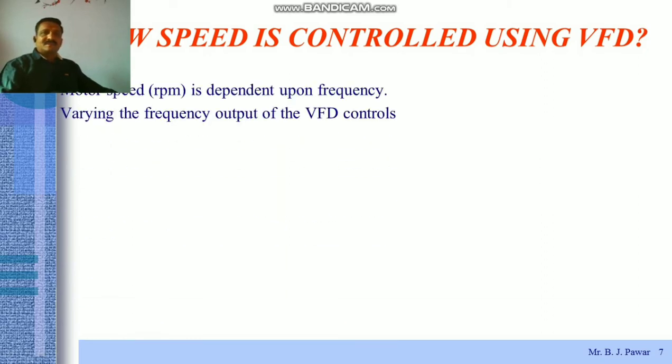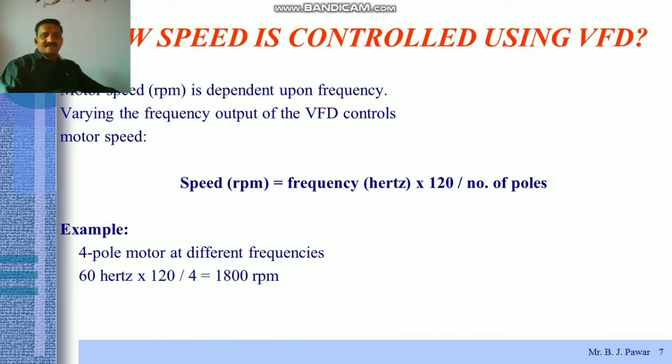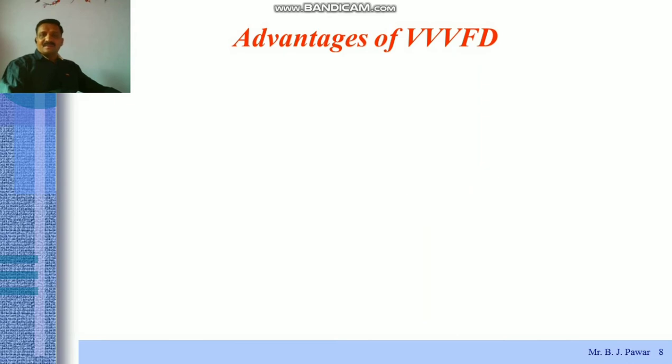So how the speed gets controlled using this VFD? Here few points are highlighted. Motor speed, that is RPM, is dependent upon the frequency of that AC supply. By varying the frequency output of that VFD, gets controlled. Then the motor speed, that is in RPM, which is equals to frequency in Hertz into 120 divided by number of poles. These are the derived equations which you already learned. So for example, suppose there is a 4-pole motor which is operated at different frequencies, that is by the output of that inverter. If it is of 60 Hertz, then that motor will get operated by 1800 RPM. That 4-pole, 3-phase induction motor will get operated by 1800 RPM. If the inverter output is set to 50 Hertz, then the speed of that motor will get changed to 1500 RPM like this. And similarly for 40 Hertz, then it will drop to 1200 RPM only.